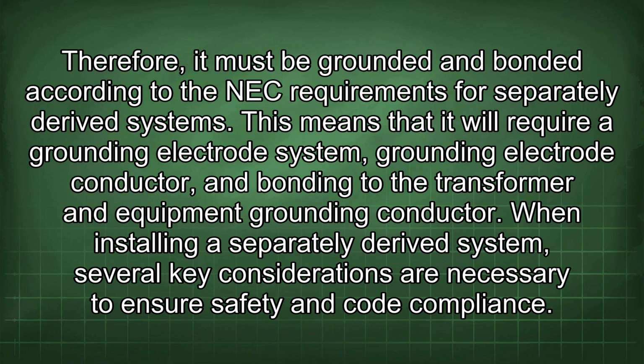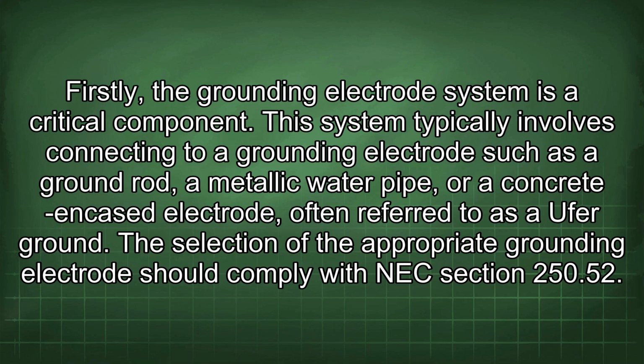This means that it will require a grounding electrode system, grounding electrode conductor, and bonding to the transformer and equipment grounding conductor. When installing a separately derived system, several key considerations are necessary to ensure safety and code compliance. Firstly, the grounding electrode system is a critical component. This system typically involves connecting to a grounding electrode such as a ground rod, a metallic water pipe, or a concrete-encased electrode, often referred to as a Ufer ground.